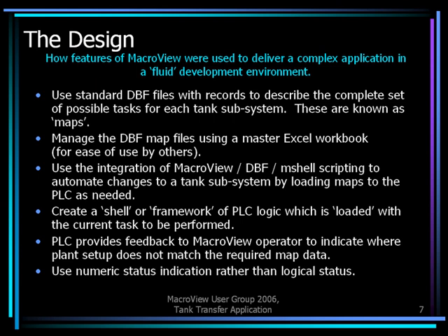We're extending that to create databases which are maps of the valves and equipment that are involved with any defined tank transfer, tank operation that you may wish to design. We're going to manage those DBF files using an Excel spreadsheet. That means we can give that Excel spreadsheet back to the process engineer responsible, and while they understand what's going on in that spreadsheet, they can approve the data inside that spreadsheet for being loaded into their plant as a way to operate it.